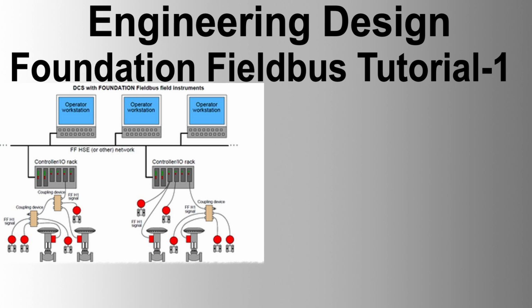Installation phase. Fieldbus offers reduced installation and material cost by replacing the traditional one-to-one wiring scheme with networking or multi-drop configuration, while intelligent field instruments make commissioning and plant startup much faster and less expensive. Operation phase. Fieldbus integrates various installations of control functions into one system to effectively optimize control of your plant. In addition, a unified human-machine interface, HMI, is provided for your operation. Function blocks allow control functions to migrate into field devices, allowing control functions to move to the field.